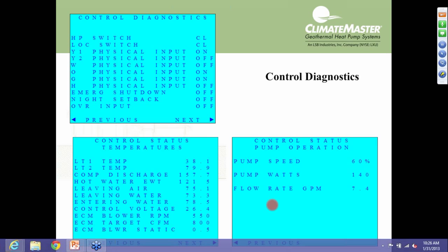Okay, the next screen under control diagnostics, there are 3 screens, will be our control status temperatures. This is where you can see all your temperatures, LT1, LT2, and so forth. I'm not going to read every one of those. Entering water, leaving water. You can see your control voltage. That can be very helpful if we've got a voltage issue going on. You can see your blower RPM and your targeted CFM.